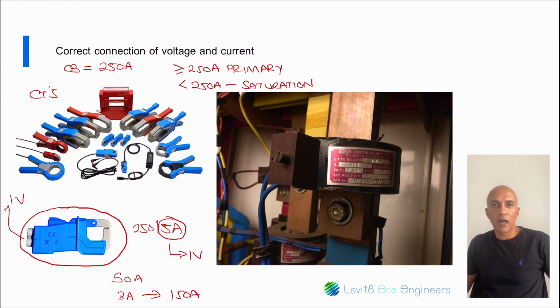Now panel CTs are mostly primary current 5 amp, such as 500 to 5. In some cases, you get primary current of 1 amp. This photo here is a 1600 to 5 amp CT, and it's connected onto the low voltage bus bar of the feeder. So it will either be on a bus bar or on the cable coming out of the main circuit breaker. We will touch on the instrument configuration sections later when discussing the installation and recording. These will differ between instruments, but we will cover some of the basic settings to look for.